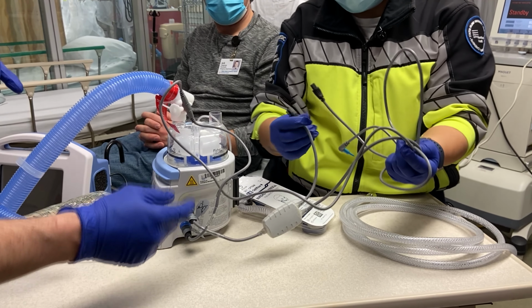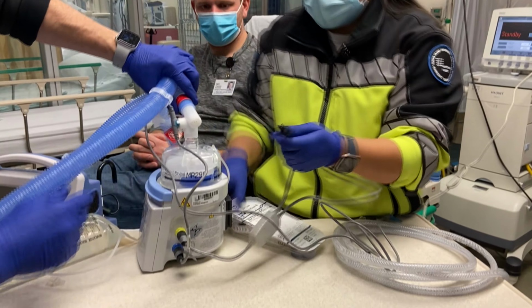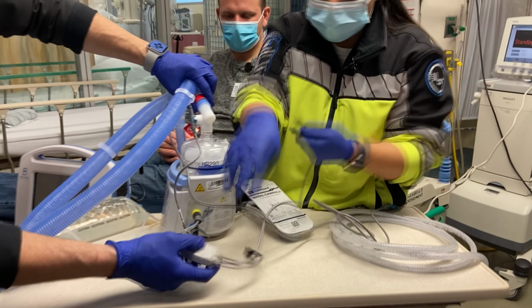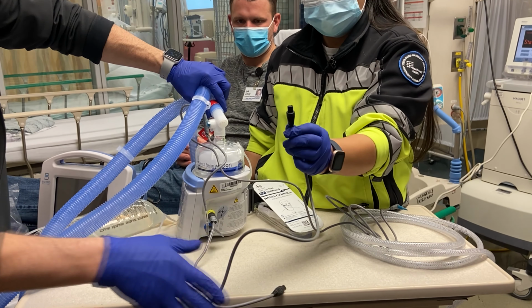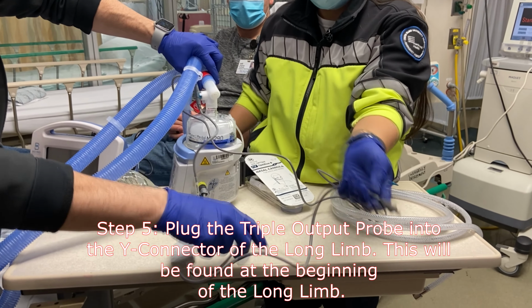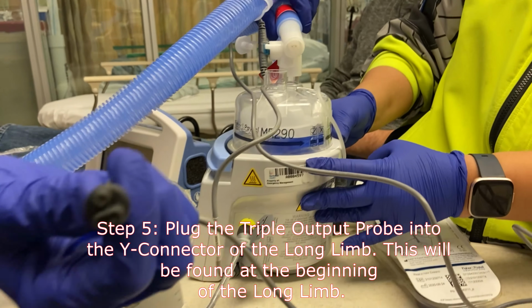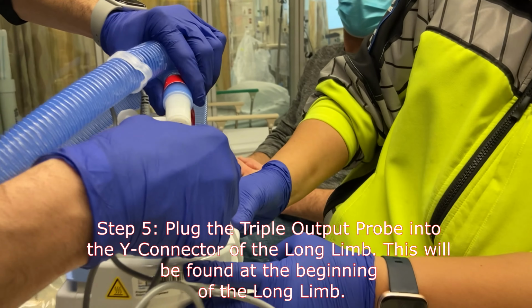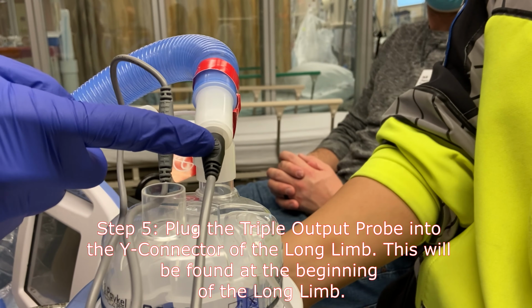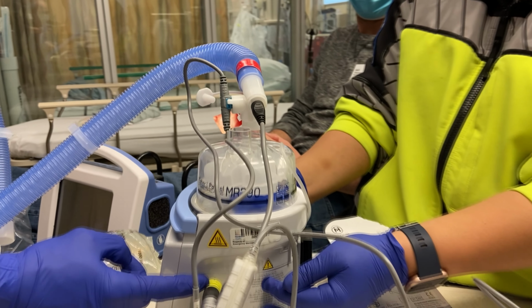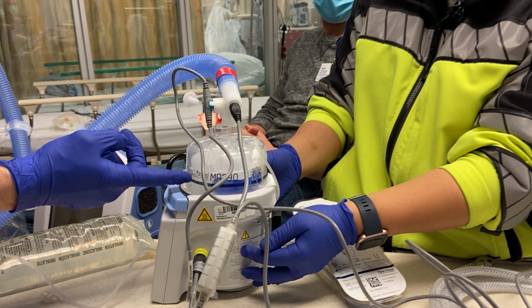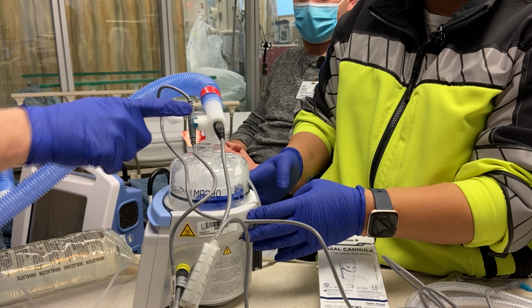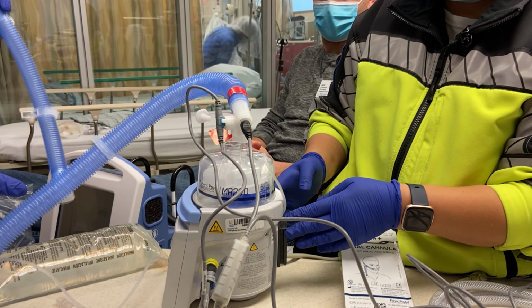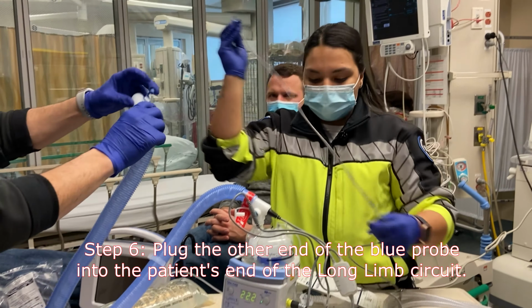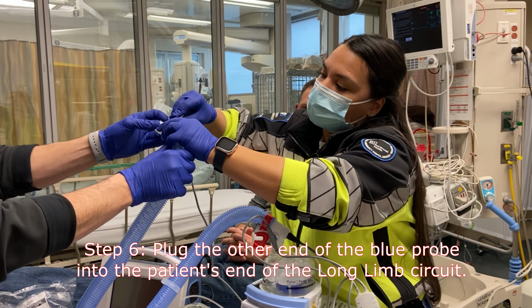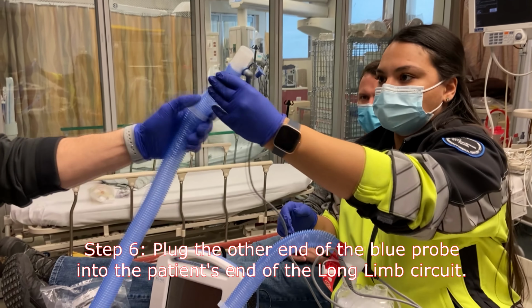So the yellow, the triple, here it is, plug. Now, mind you, this heater has 2 outputs, one of which we're not going to use. The dual output just is to be ignored. The triple output goes into the corresponding plug on the beginning of the circuit. This is what provides heat to the circuit from the device with the humidified inhalation sterile water coming out of the circuit, and the sensor to modulate the temperature as needed to reach your intended goal. So this prong is going to go into here, into your circuit, the patient end of the circuit.